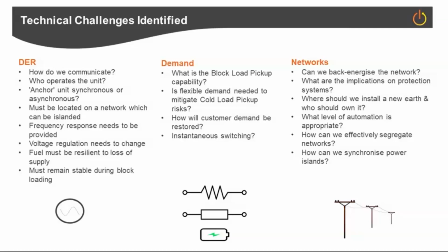There's a challenge around fuel. There needs to be enough fuel for that generator to be running for a number of days, and able to allow the wider network restoration to proceed. And I think stability. The generator has to be stable, and that's key during the phase of applying the demand, in block loading capability. So there's quite a number of challenges there for generation.